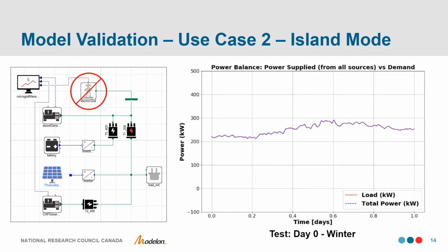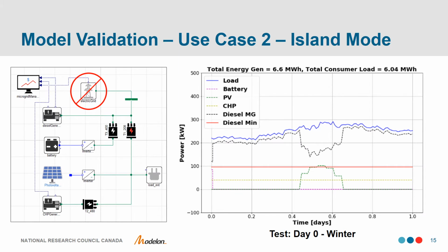To validate our simulation results for use case 2, we looked at 2 seasonal cases, one day in the winter and one day in the summer. To start off, we did a simple power balance to make sure that the power supplied from all sources matched the consumer demand. In this chart, you can see that the CHP system is providing the continuous 40 kilowatt output, allowing the diesel generator to track below the overall load compared to the runs that we saw with the diesel-only configuration. As the PV power comes online, you can see the corresponding decrease in the diesel generator output, which is what we would expect.